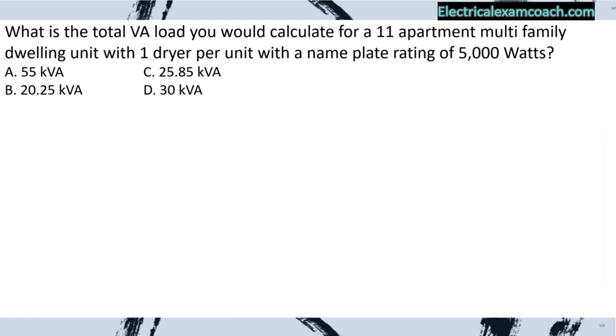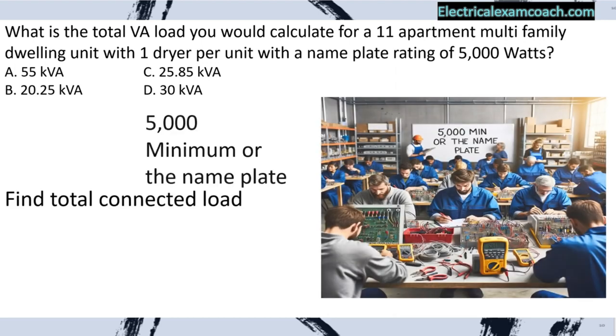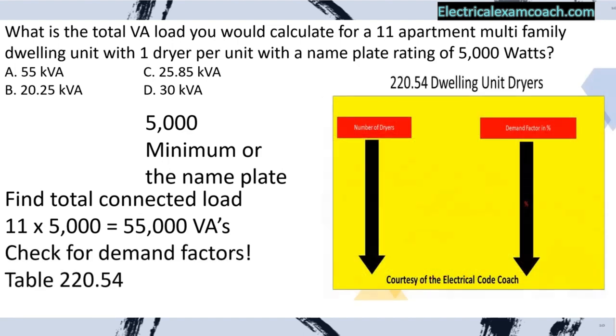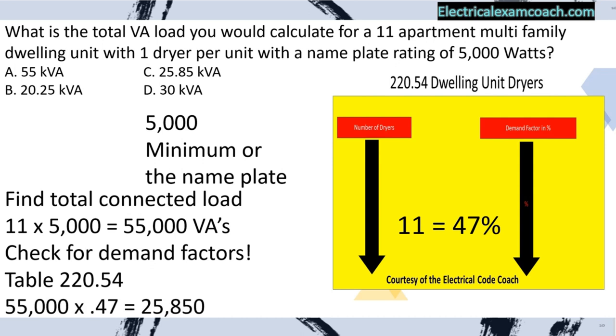Practice problem: What is the total VA load for an 11-apartment multifamily dwelling unit with one dryer per unit and a nameplate rating of 5,000 watts? Find the total connected load: 11 units multiplied by 5,000 equals 55,000 VAs. Check for demand factors per Table 220.54: the demand factor for 11 dryers is 47%. We take 55,000 multiplied by 0.47, giving a new reduced load of 25,850 VAs. We select C.